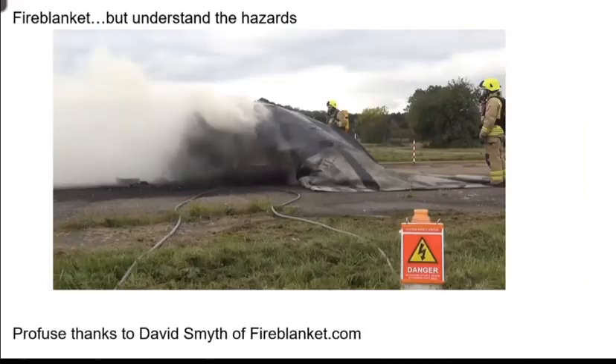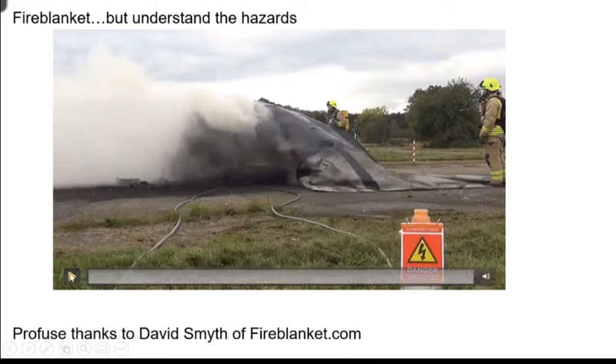So this is fire blankets. They do have a role, but you need to understand the hazards. These fire officers didn't. They think the white stuff coming through the blanket is smoke, therefore it's not explosive. It isn't. They've thrown the blanket over an electric vehicle on fire. It's killed the flames, but the cells are still in thermal runaway because there's no cooling, and they're boiling off the vapor cloud. They then pull back the fire blanket.